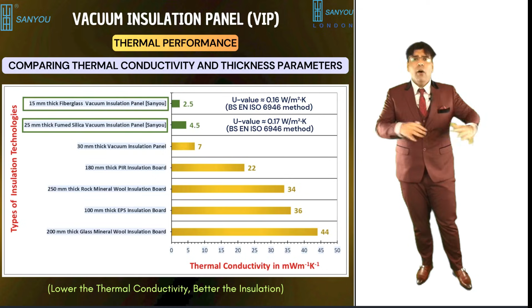For example, even at 250 millimeter thickness, rock mineral wool still has a thermal conductivity of 34. Similarly, glass mineral wool at 200 millimeter shows a thermal conductivity of 44. PIR at 180 millimeter thickness has a thermal conductivity of 22. And as for EPS, even at 100 millimeter, it reaches a thermal conductivity of 36 milliwatt per meter per Kelvin. So even at thinner dimensions, VIPs outperform all in terms of insulation, but again, what does it mean?